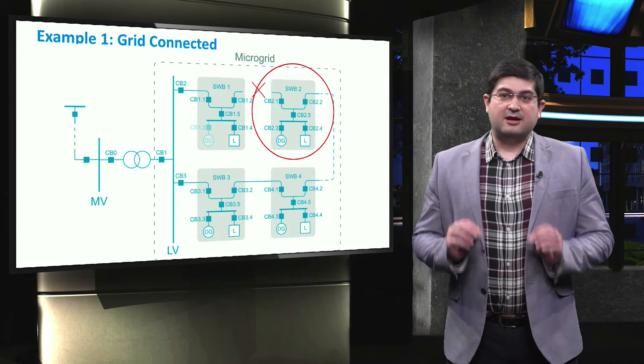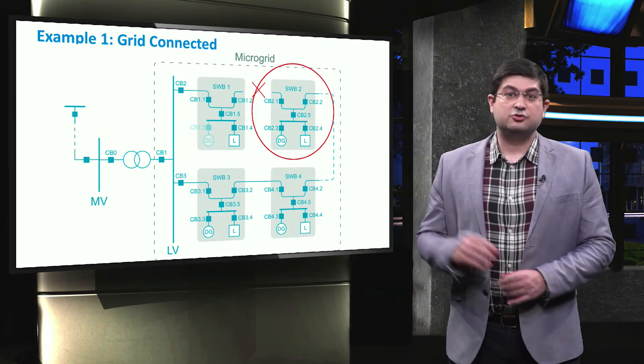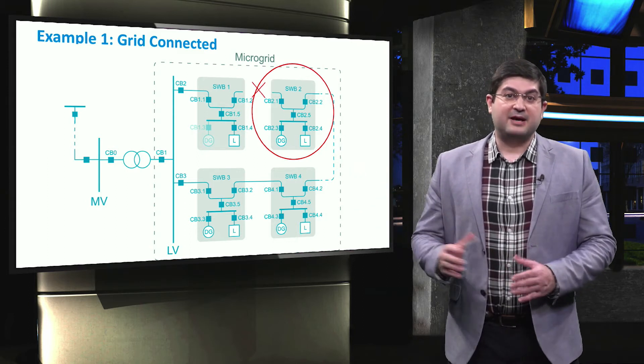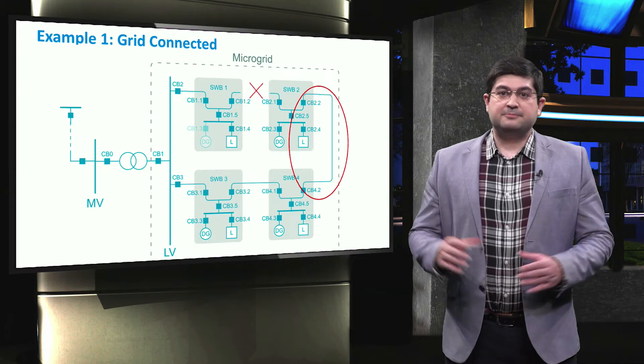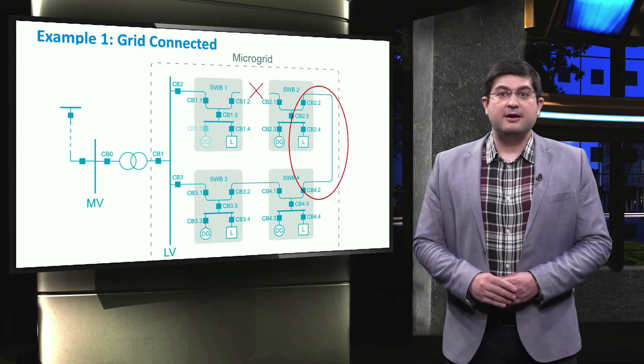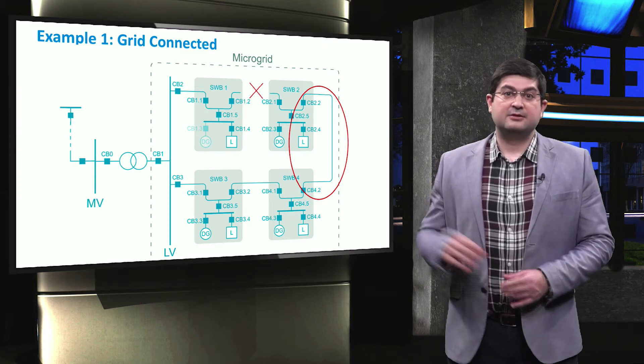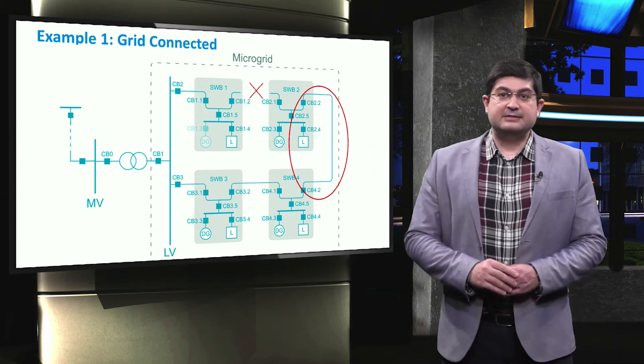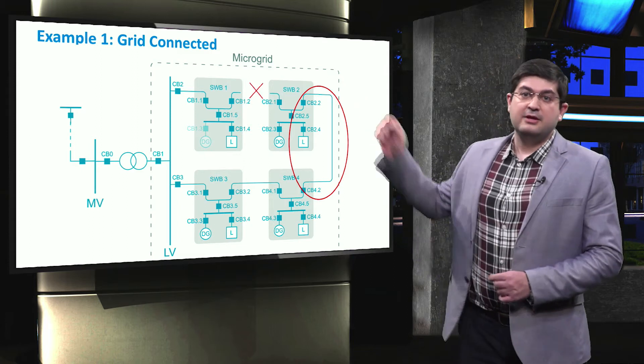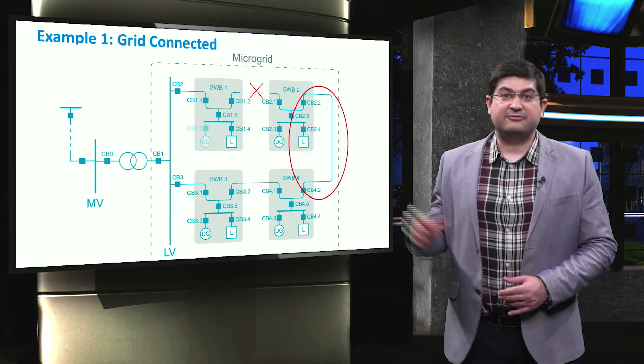To increase the reliability and reduce the time period of the disconnection of switchboard 2, it can then be connected to the grid through another path. Circuit breakers 2.2 and 4.2 are closed, and therefore switchboard 2 is connected to switchboard 4. This ensures that switchboard 2 will have supply of electricity as soon as possible after the fault.